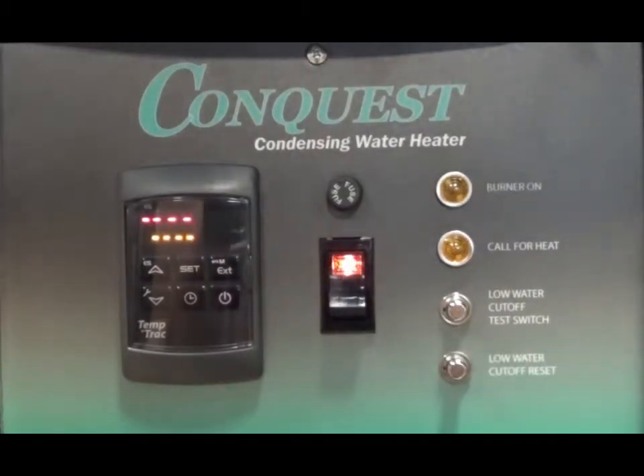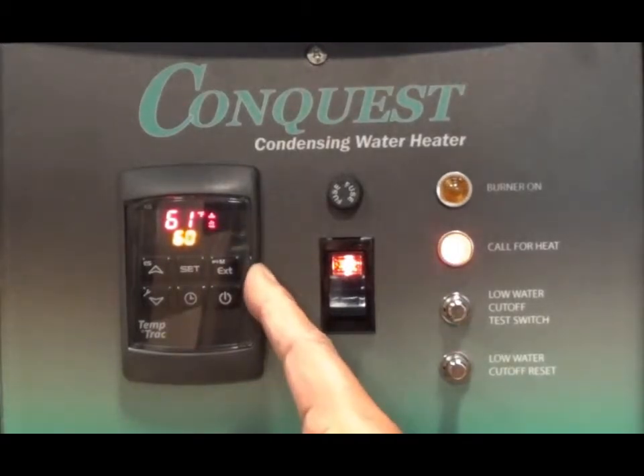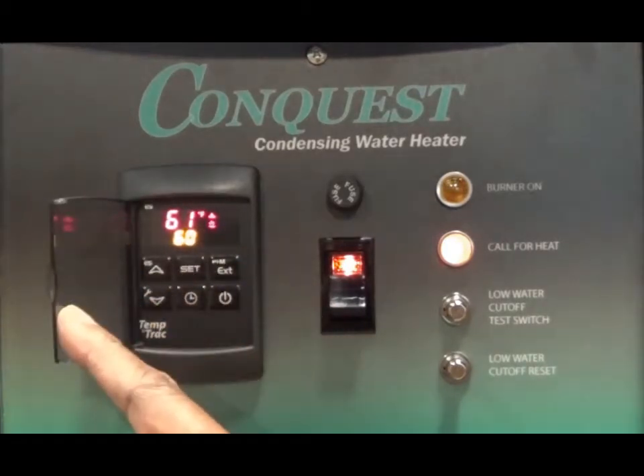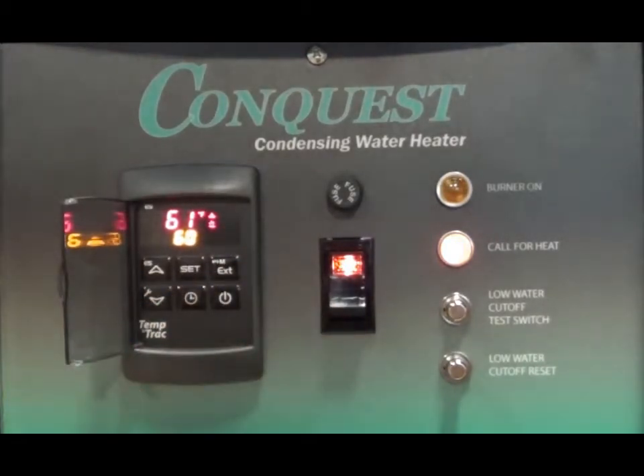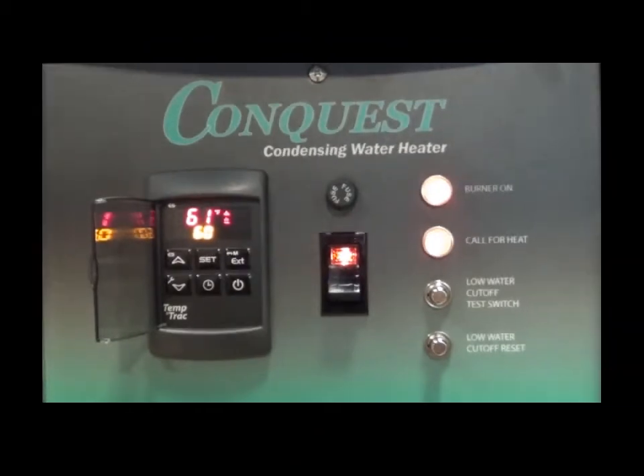Open the main gas valve to the burner. Now turn the CONQUEST power switch to the on position. Following a 30-second pre-purge and 20-second hot surface igniter heat-up period, trial for ignition is initiated. The burner on light on the control panel will illuminate when the trial for ignition begins. Flame is proven and the burner should continue to fire until the tank reaches the set point temperature.